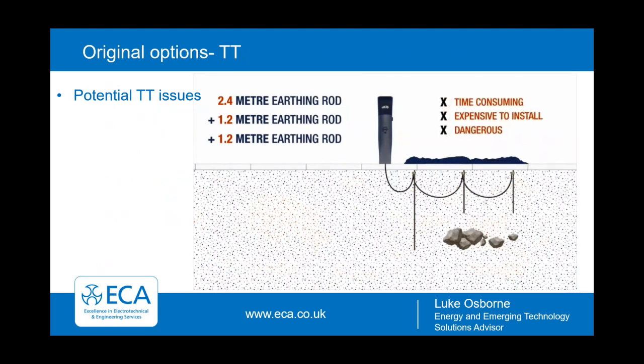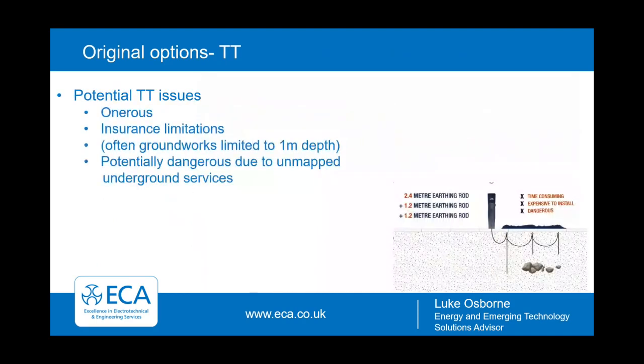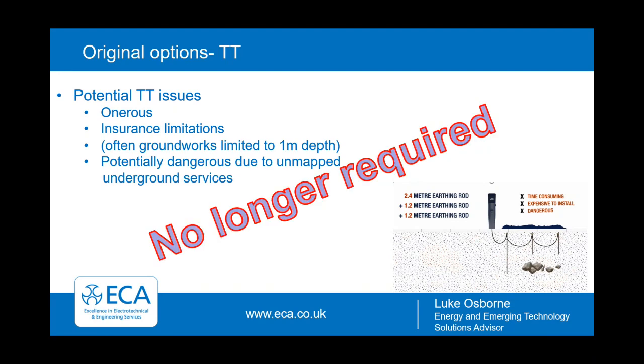So not the easiest of options to use, but it is there nonetheless. But it is an onerous operation. There's also insurance limitations to consider, often for the electrical contractor. Unless specified in your insurance, the groundworks could be limited to 1 meter's depth. But crucially, it's potentially dangerous due to unmapped underground services. Luckily, through Amendment 1, this is no longer required.